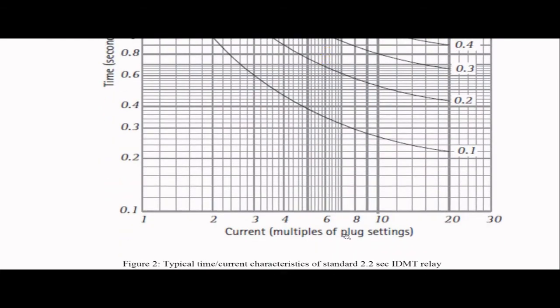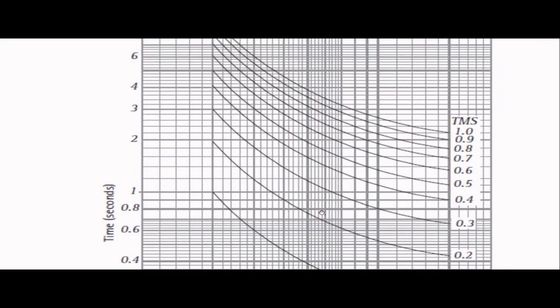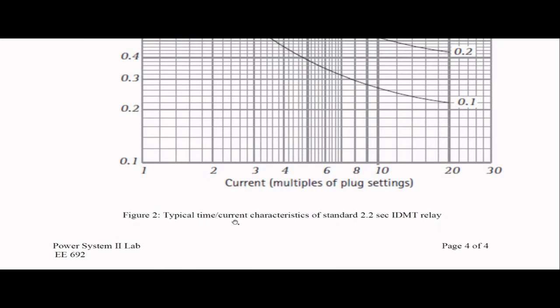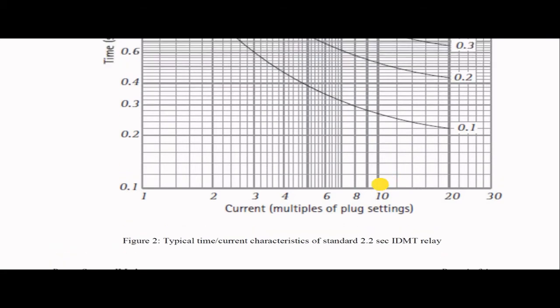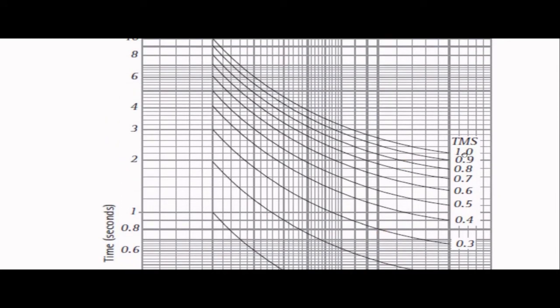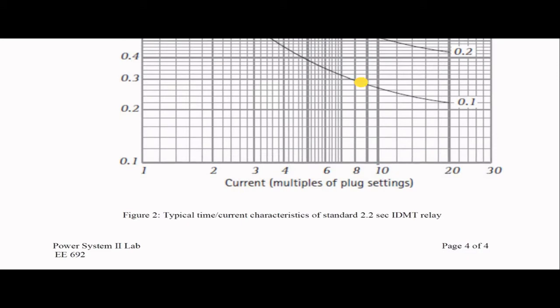And this axis, as I mentioned, is called the plug setting multiplier. The plug setting multiplier is the relay current divided by the plug setting of the relay. So it may be 1, 2, 3, 4, 5, 6. The name of the characteristic could be the typical time current characteristic of a standard 2.2 second IDMT relay. Now why is it called 2.2 second? Because if the time multiplier setting is fixed at 1.0, then from the first graph you see the minimum time required, which is 2.2 seconds. So a minimum of 2.2 seconds is required to operate the relay. That's why this is called the 2.2 second IDMT characteristic.